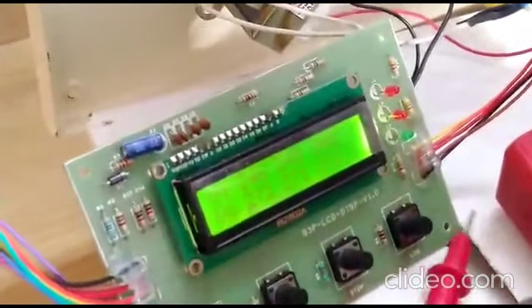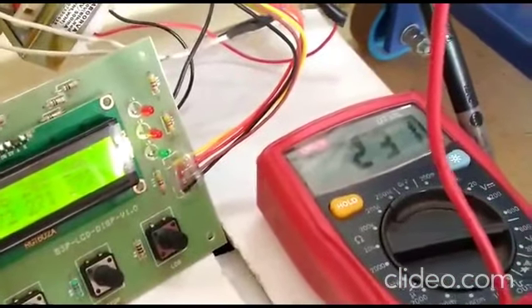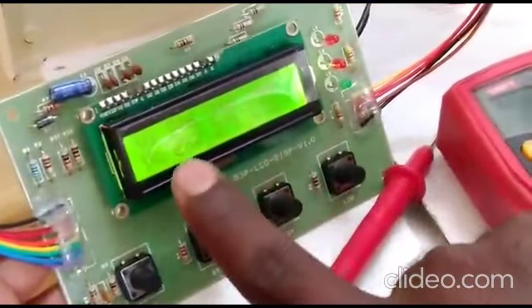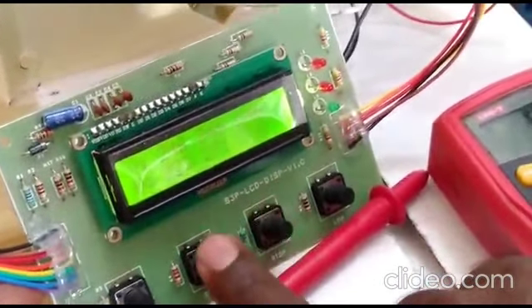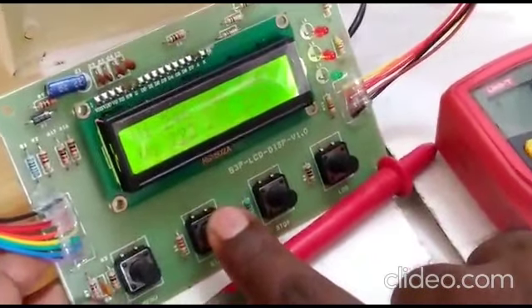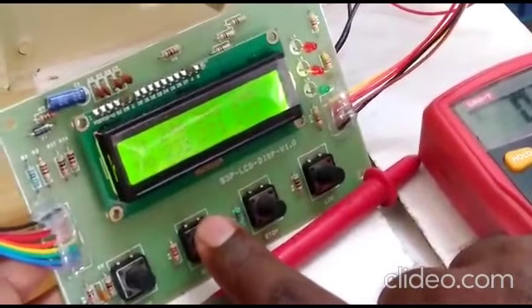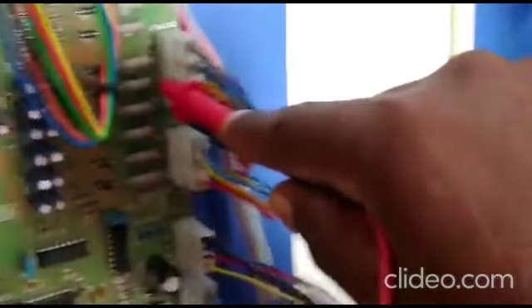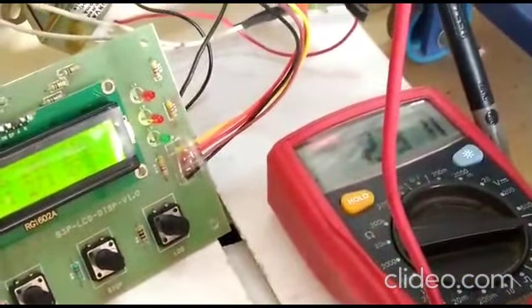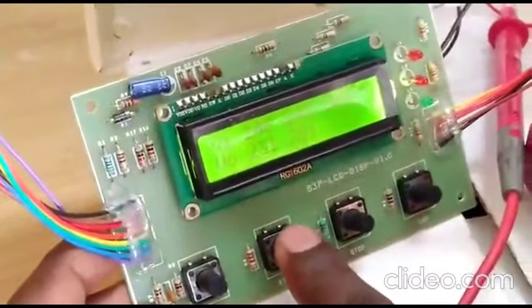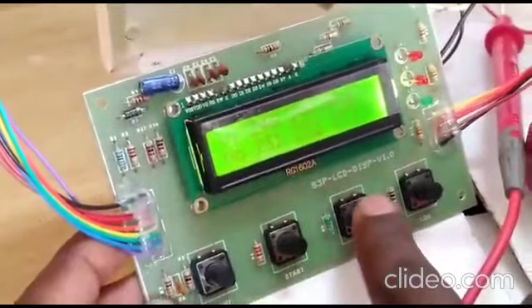Next, we are going to set the output voltages. For output voltages, measure from this resistance. Output R phase voltage is 231. We should set 231. The next one is output Y phase voltage, which is 232. Output Y phase voltage is 232. And the next is output B phase voltage.